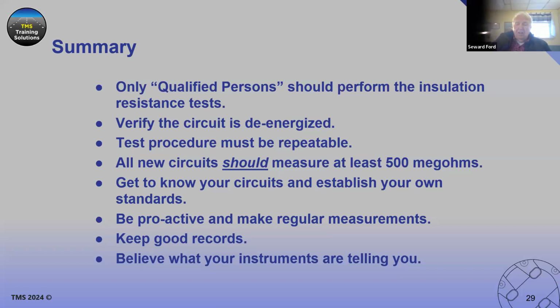We know what is suggested. We're saying generally a 1,000 volt Megger test is adequate for finding faults, but you want to maintain that same voltage check all the time because you're looking for a trend. The leakage developed today in a test may have been magnified the next time you do the test. So you keep all the parameters the same, and you must do it on a regular basis. Be proactive and make regular measurements. We've said that. Keep good records.